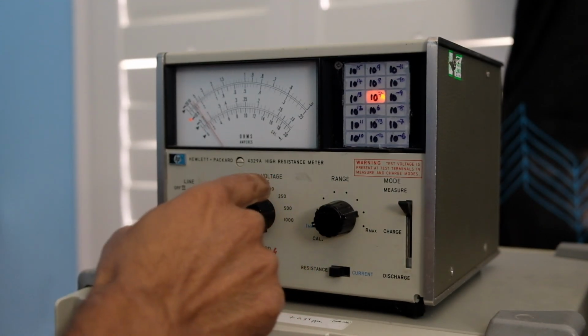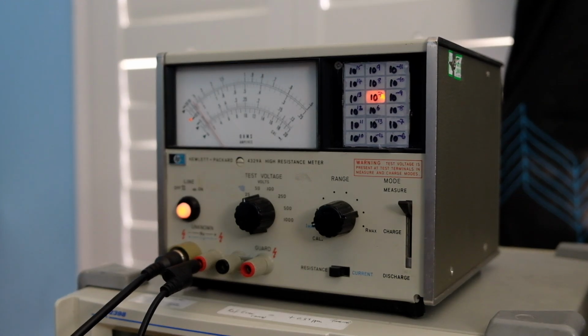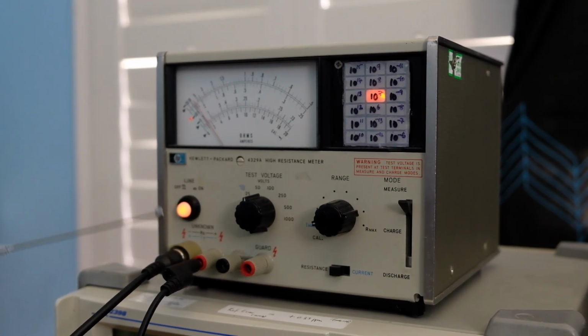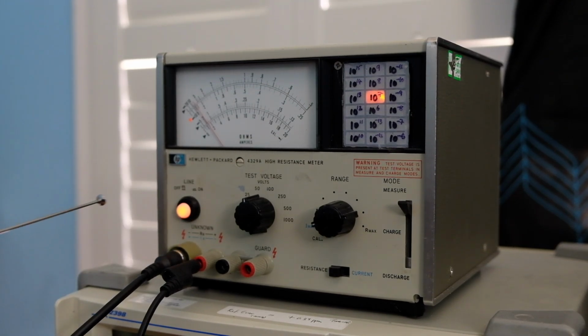Of course, you've got to be careful when you're operating anywhere above 100 volts that you shield yourself, and don't touch the terminals while it's being measured. You do need a good cable here with the outer guard and everything, which I don't have, and those cables tend to be more expensive than the instruments themselves these days. In terms of polarity, for resistance measurements the positive voltage is applied on this node, and the center conductor of this BNC is the negative return current node for the resistor. For current measurement, the positive current comes out of this center, and the negative is on this particular terminal over here, so it's reversed.